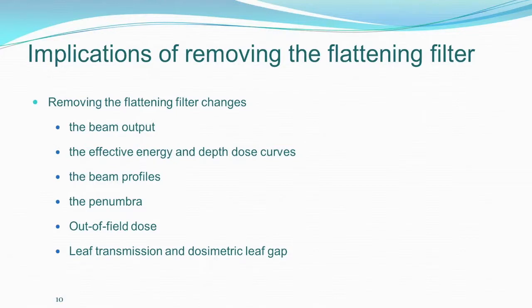What are the implications of removing the flattening filter? I talked earlier about the implications of having a flattening filter. Now, what are the implications of removing it? It's not just easy to remove, right? I used to jokingly say that when you remove a flattening filter, the cost of the LINAC goes up, but there are some implications actually. When you remove the flattening filter, the beam output increases, which we know very well, because there is no attenuation by the flattening filter. The effective energy is now decreased, so the depth dose characteristics will be different.